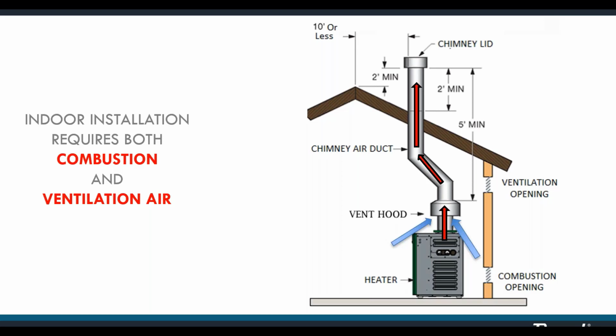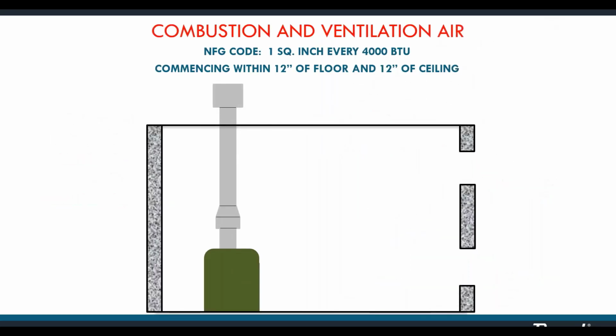In this configuration, that draft hood, when the heater's running, starts to suck the air out of the room. It's pulling air out of that room like a vacuum cleaner. We have to replace that air. Replacement air comes in through a ventilation opening at the top of the wall. That is our ventilation opening for ventilation air, sometimes referred to as replacement air. So the NFGC has guidelines for this. All right, those are dictated by the National Fuel Gas Code.